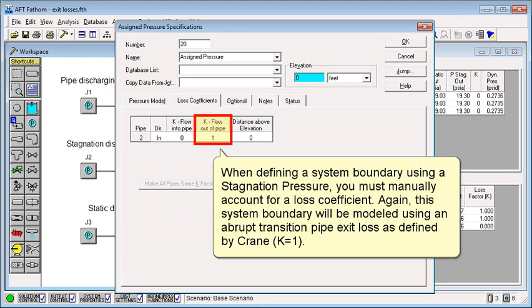When defining a system boundary using a stagnation pressure, you must manually account for a loss coefficient. Again, this system boundary will be modeled using an abrupt transition pipe exit loss as defined by Crane.